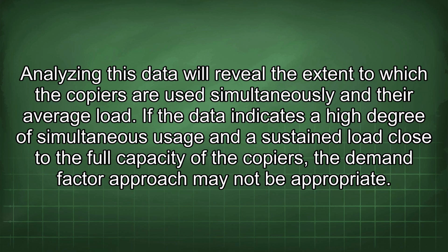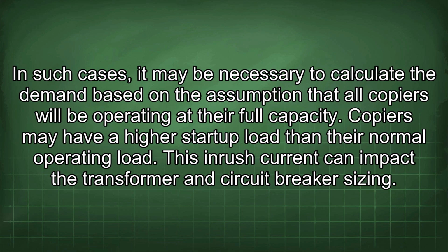If the data indicates a high degree of simultaneous usage and a sustained load close to the full capacity of the copiers, the demand factor approach may not be appropriate. In such cases, it may be necessary to calculate the demand based on the assumption that all copiers will be operating at their full capacity.